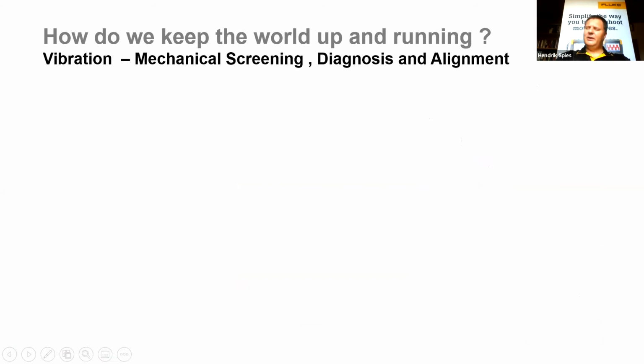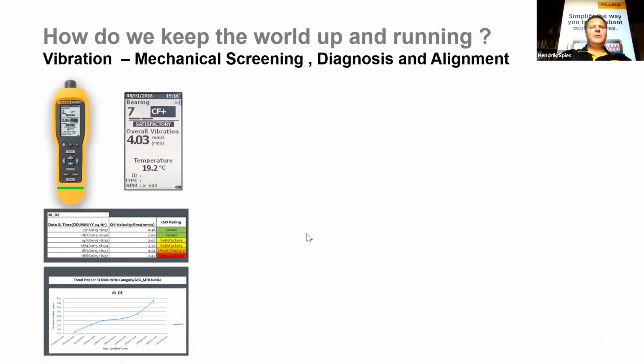Okay, so let's look a little bit at vibration. If you look at vibration, we've got the screening tool, which is the Fluke 805, which typically will look at bearing condition and overall vibration of the total installation. So if you've got that pump with the actual motor with the coupling on a skid, it looks at the overall vibration as well. And as you can see here, as we take measurements as preventative maintenance every 6 months, every year, we start to build a library of measurements which will show us the aging over time.